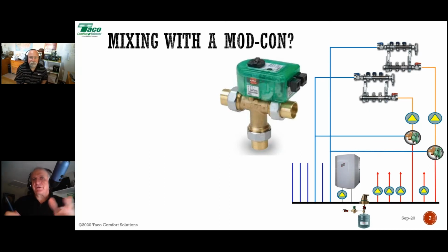boiler. A lot of folks will look at ModCon boilers and say, great, it's a low temperature boiler. If I make all of my different outputs, so say I got some high temp, some radiant and some radiators, if I make that all one temperature, the boiler reset will be fine and I don't have to mix or anything like that. And there's an attraction to that because it's simpler, right?